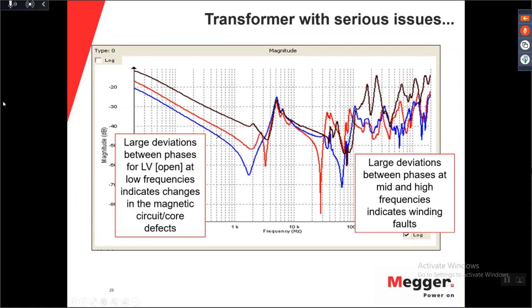Because here you don't have the typical behavior of an open test. Two should be similar, but here all three are different. All curves should align here. And here I see large deviation between all phases, and that is actually indicating some type of winding fault. So this is seen quite clearly from only one measurement.